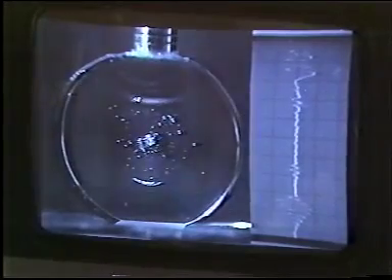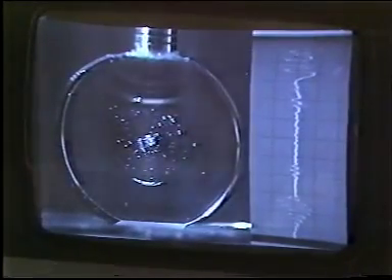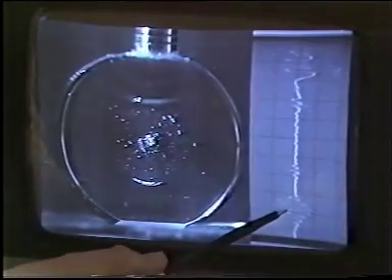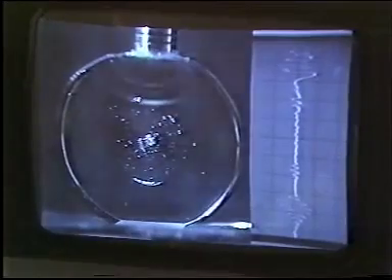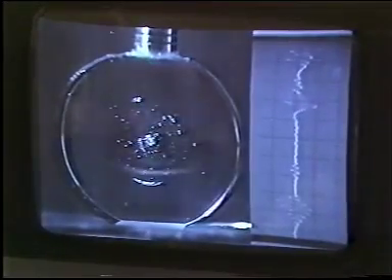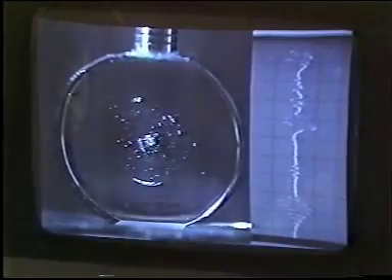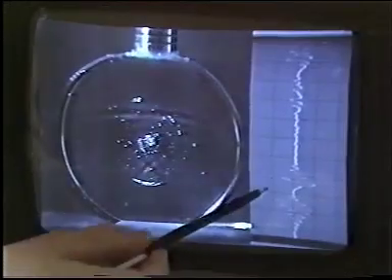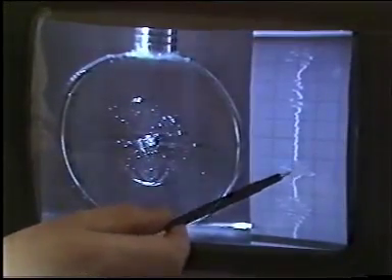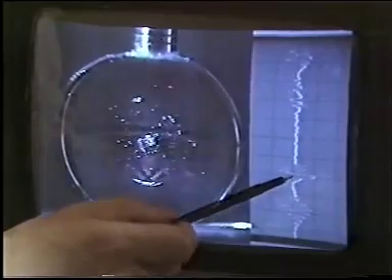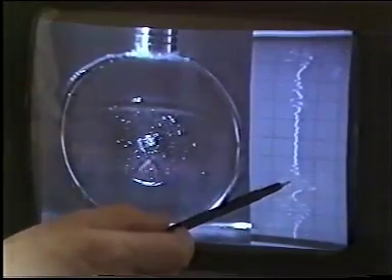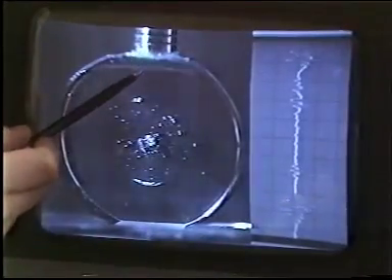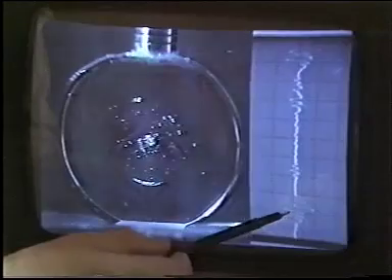I'll switch on again. Now, I'm showing the oscilloscope waveform at the same time. So there's that echo I was talking about from the bottom. And to remind you, let's move the visualization system delay so that we see the echo hit the bottom and come back up to the top. Now, you'll notice while I'm doing this, there's a waveform which is moving through there, which is breakthrough of the signal which triggers the lamp. So, in fact, you can see that we're triggering the lamp now. At that time, when the signal hits the transducer again, which coincides with the received signal.